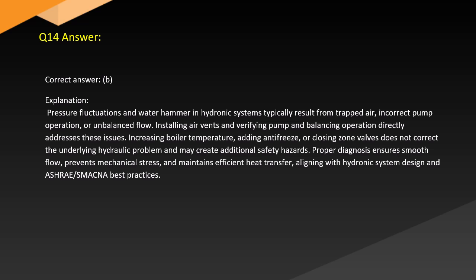Increasing boiler temperature, adding antifreeze, or closing zone valves does not correct the underlying hydraulic problem and may create additional safety hazards. Proper diagnosis smooths flow, prevents mechanical stress, and maintains efficient heat transfer, aligning with hydronic system design and ASHRAE and SMACNA best practices.